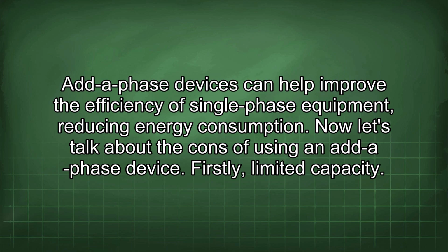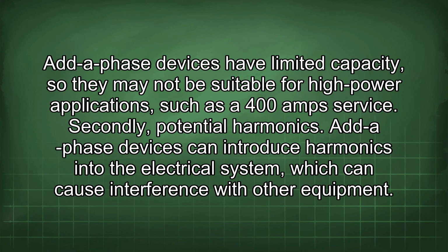Now let's talk about the cons of using an add-a-phase device. Firstly, limited capacity. Add-a-phase devices have limited capacity, so they may not be suitable for high-power applications such as a 400 amp service. Secondly, potential harmonics. Add-a-phase devices can introduce harmonics into the electrical system, which can cause interference with other equipment.